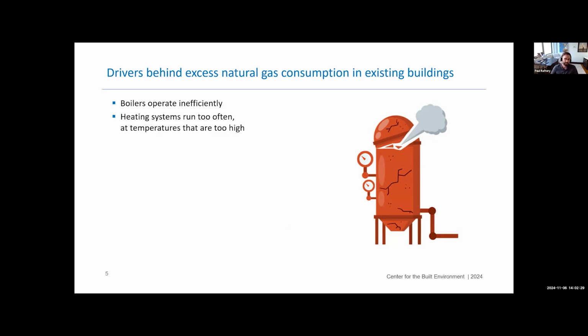Another one is that heating systems often run way too frequently in buildings, and they often run at temperatures that are very high. Anecdotally, we had seen that many buildings run their hot water system 24/7, 365 days a year, which is obviously wasting a lot. So we wanted to see how prevalent that was. And we also wanted to see how much of an impact that was having, right? So a lot of the time when folks analyze these systems, they just kind of minimize or entirely neglect the amount of energy it takes to keep all of that hot water piping hot inside the building. Even if you're not using any of it, it still wastes a little bit of energy.